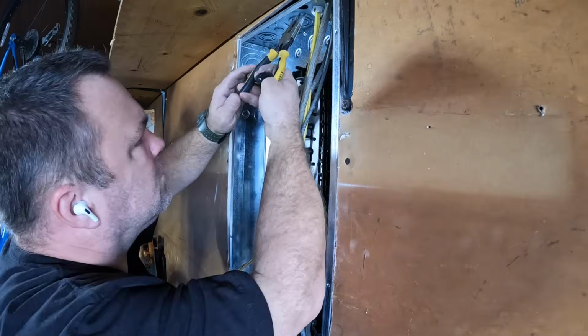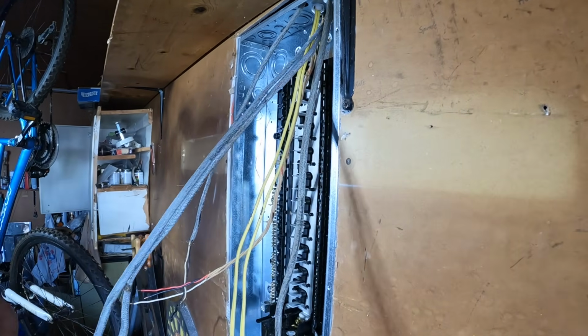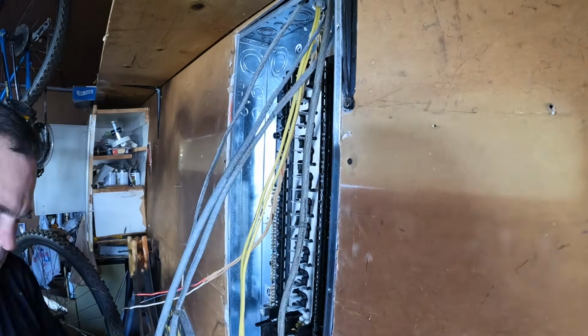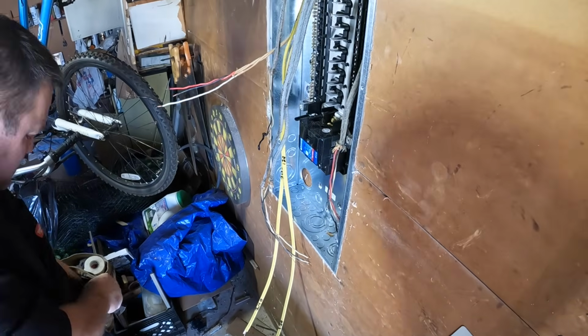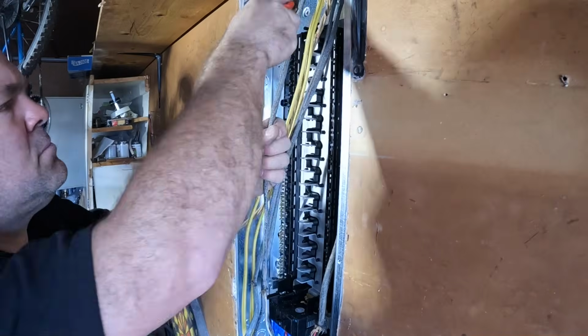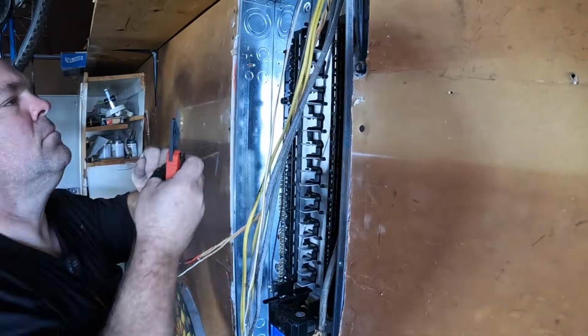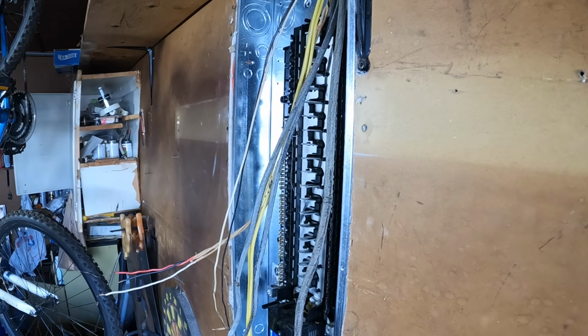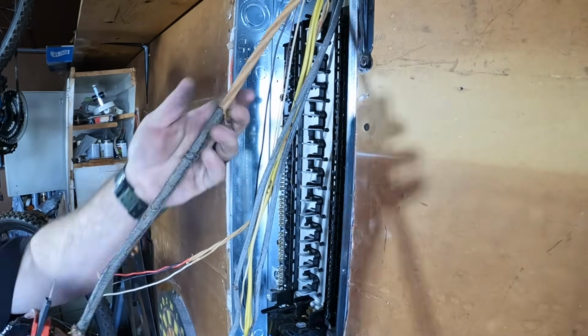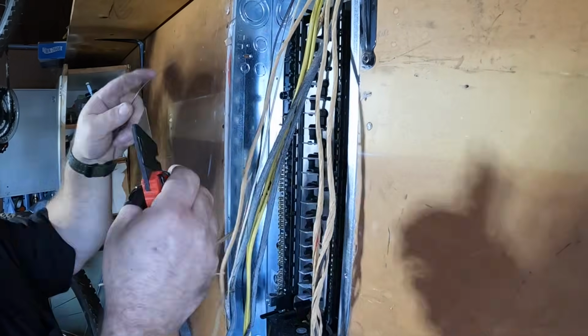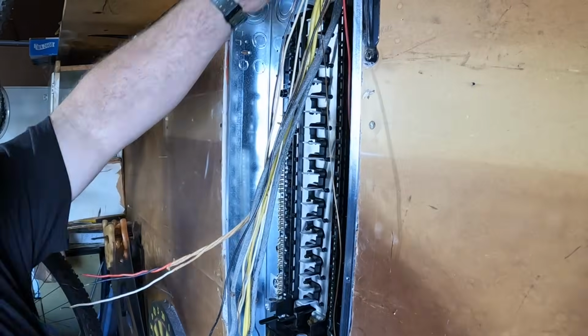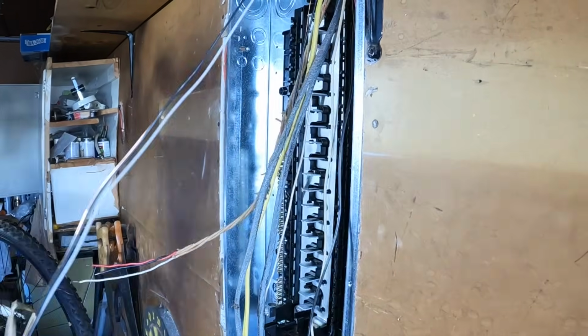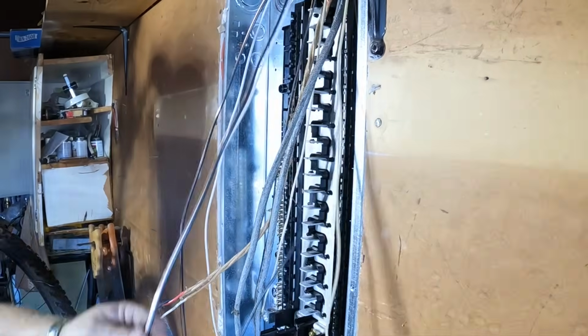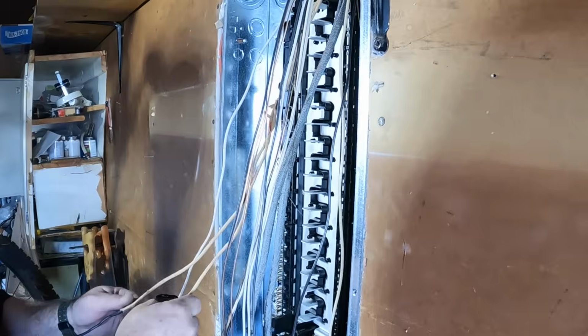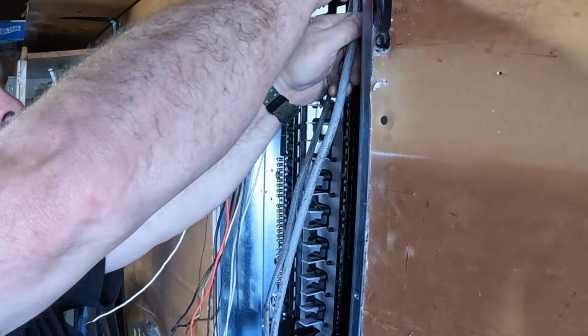Now, because I have my main disconnect on the outside of the house, this is what's known as a 4-wire setup, or a main lug only. We call it subpanel. There's nothing in the National Electrical Code that mentions anything about a subpanel, just panel boards. But this is actually a main breaker load center. And the reason why I leave the main breaker in there is because if we want to install an interlock later on for portable generator wiring, it's all set and ready to do that. This costs me, as the contractor, about $20 more to provide the whole main disconnect assembly enclosure here, rather than just getting a 40 circuit main lug only 200 amp panel. It's just easier and a better installation to keep the main disconnect, or the main breaker, inside this panel.